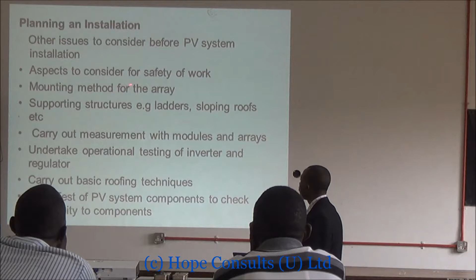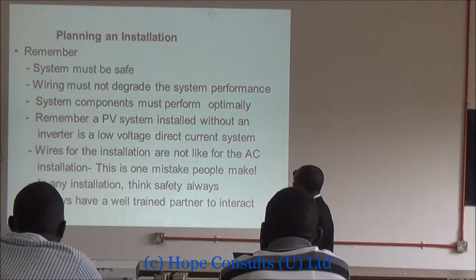Consider supporting structures like ladders and sloping roofs, carry out measurements with modules and arrays, undertake operational testing of the inverter and regulator, carry out basic roofing techniques, and field test PV system components to check conformity. Test the open voltage and short circuit current before putting your system to use.